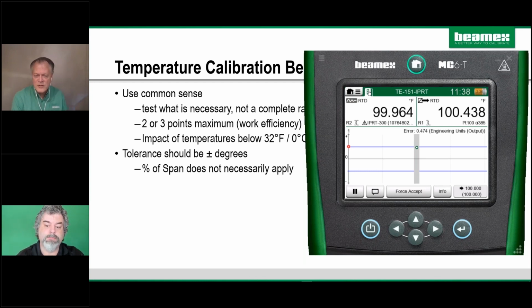So how do you adjust it, Roy? Is there like a little screwdriver adjustment? Oh yeah. So we need to, you take it. Actually, you can't. Yeah, there's no adjustment. Well, pipeline people just simply would put in this half a degree offset into a flow computer and keep on going. But maybe half a degree is pretty significant. They might make the decision to replace it. So this probe is really marginal.